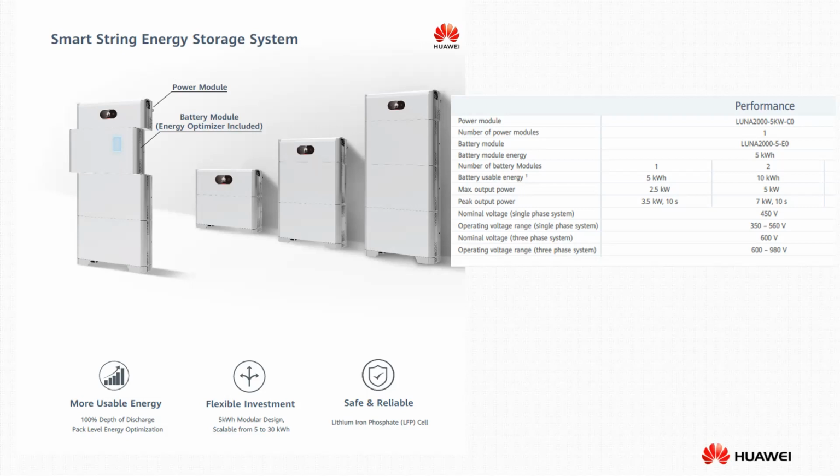Each battery module is a 5 kilowatt hour pack at 0.5 C, which means continuously you can draw up to 2.5 kilowatt at a given time. It can supply a peak power of up to 3.5 kilowatt for 10 seconds. So for all your starting currents, if you have pumps or inductive loads, the battery will be able to surge power up to 3.5 kilowatt for 10 seconds.